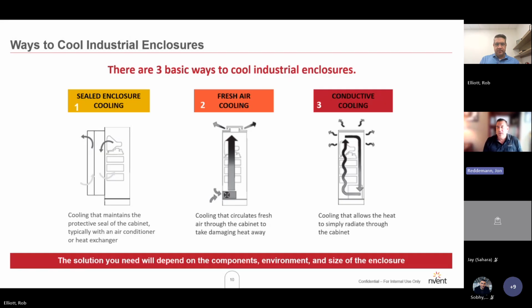When we're talking cooling, we have passive systems and we have active systems. A passive system means that our enclosure temperature can be higher than our ambient temperature, and the general rule of thumb is 10 degrees. Okay. An active system means that we need to actively drive our enclosure temperature below whatever our ambient temperature is, right? So a sealed enclosure cooling has both active and passive. Fresh air cooling is passive only, and conductive cooling is considered passive only.